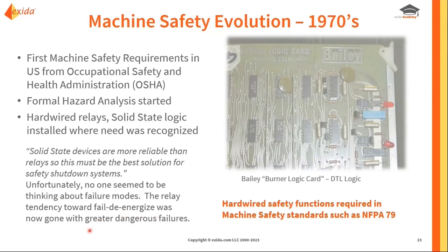You may actually see a greater percentage of solid state failures be dangerous failures. So the technology was changing, but we didn't necessarily understand the best way to apply it to safety functions. A lot of the machine safety standards were more cautious of new technologies. We'll see the NFPA 79 standard, which was used heavily in the United States, had explicit requirements that safety functions had to be hardwired — and they kept that requirement for an extended period of time.